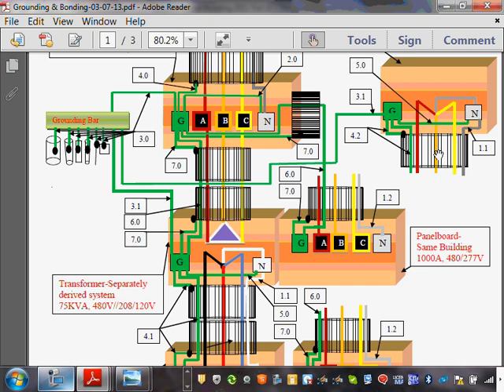Do you guys use delta generators? You've seen a delta generator? Well, I've seen plan drawings that have a generator and an automatic transfer switch, and they're only bringing three-phase wires into a grounded system through the automatic transfer switch. Was it single phase or three-phase? Three-phase, 480. I don't know what's in their mind, but I've never seen it. Doesn't mean it doesn't exist. Unless it's a delta, the only thing I can think of. Or the designer forgot to pull another wire on the feeder.